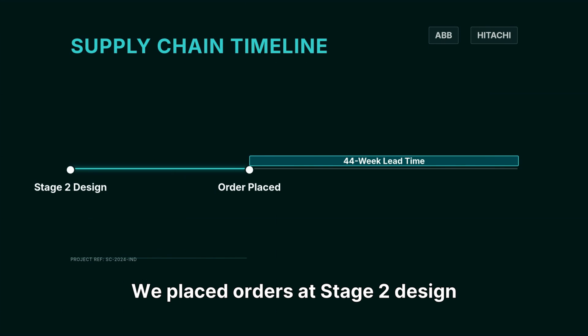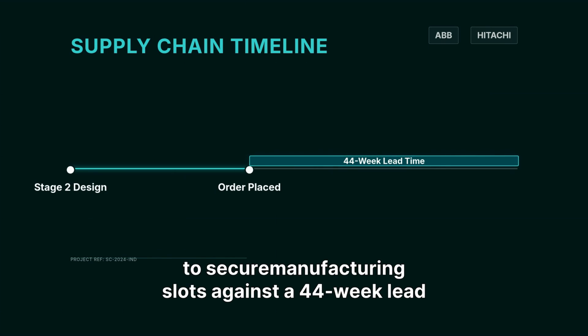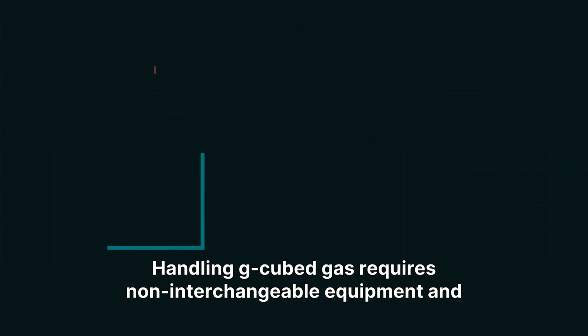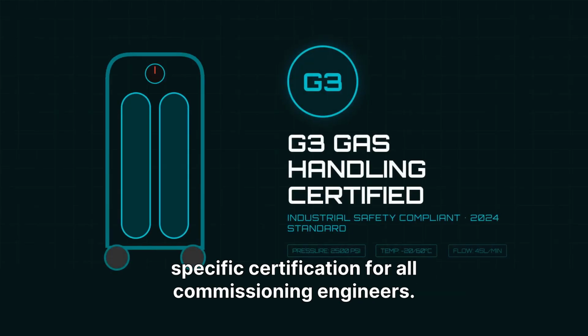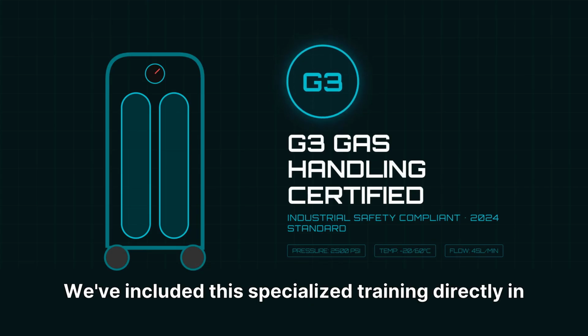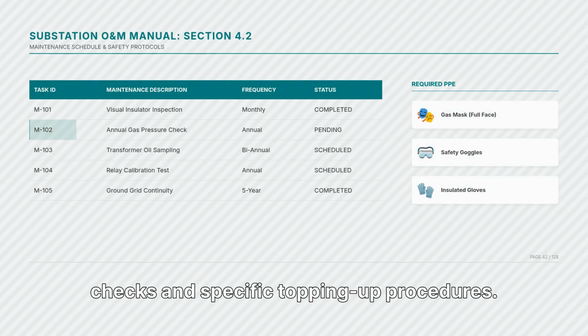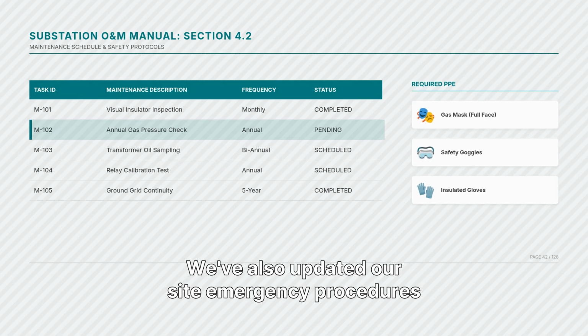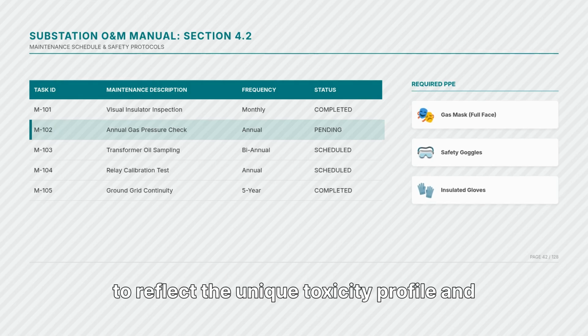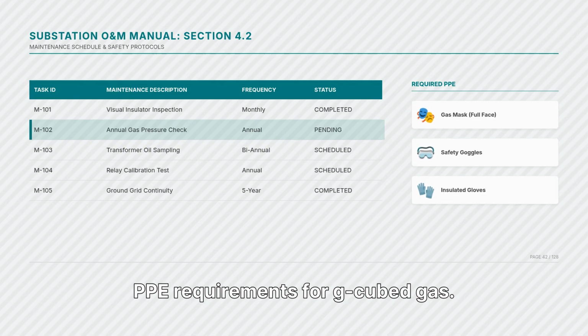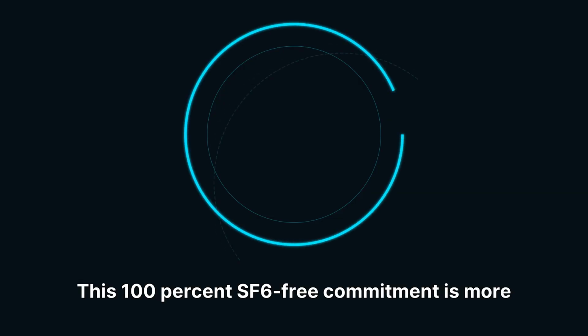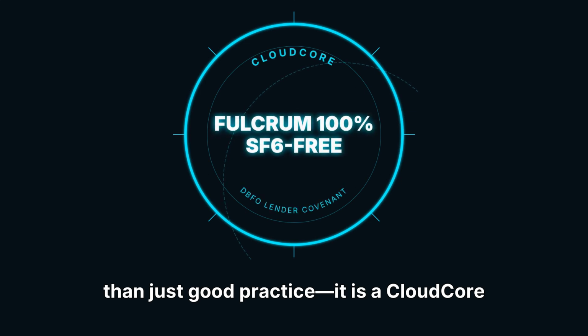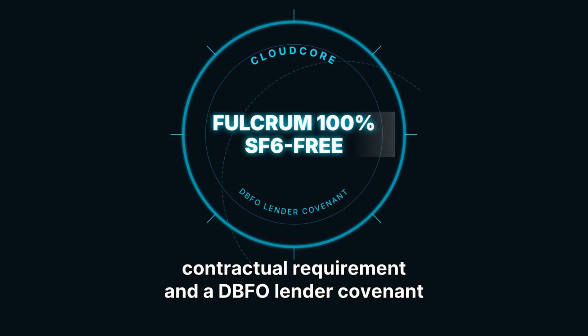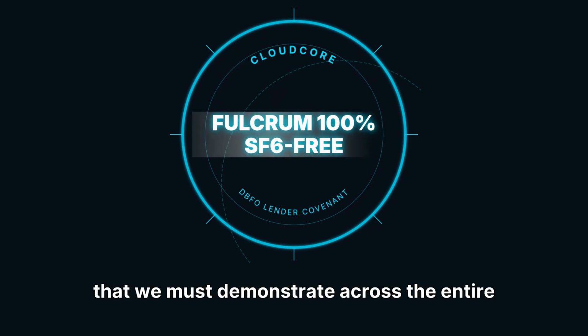We placed orders at stage 2 design to secure manufacturing slots against a 44-week lead time. Handling g3 gas requires non-interchangeable equipment and specific certification for all commissioning engineers. We've included this specialized training directly in our integrated commissioning plan. Our maintenance schedule includes annual gas pressure checks and specific topping up procedures. We've also updated our site emergency procedures to reflect the unique toxicity profile and PPE requirements for g3 gas. This 100% SF6-free commitment is more than just good practice. It is a CloudCore contractual requirement and a DBFO lender covenant that we must demonstrate across the entire campus.